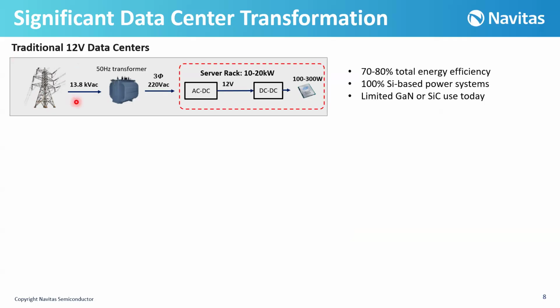At the top here we have the traditional 12-volt data centers. We step down the voltage from 13.8 kilovolt AC to 220 volt AC three-phase, utilizing a bulky and heavy 50 hertz transformer. Then we step down this voltage to 12 volts using an AC-DC converter, and finally, using a DC-DC converter, we power components like CPUs and GPUs. The power density of this server rack is 10 to 20 kilowatts, and the components use 100 to 300 watts. The total energy efficiency of this architecture is only 70 to 80%, because it's based only on silicon power devices.